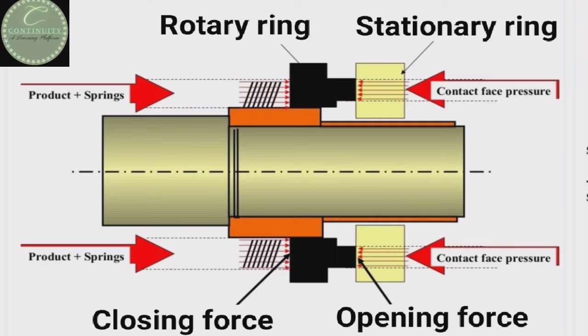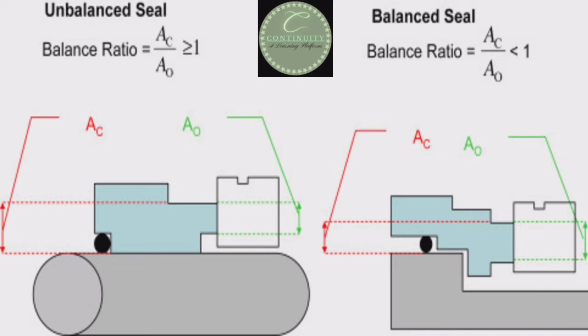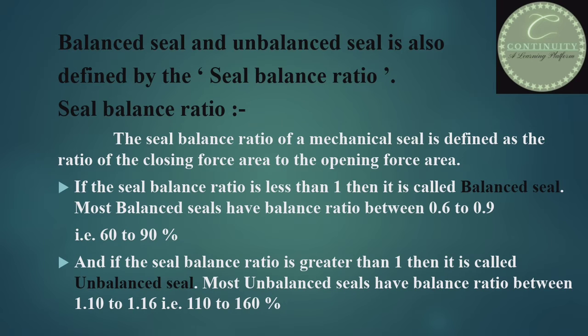Do you know that balanced seal and unbalanced seal are also defined by the seal balance ratio? Yes, it is also defined by the seal balance ratio. Seal balance ratio of a mechanical seal is defined as the ratio of the closing force area to the opening force area.